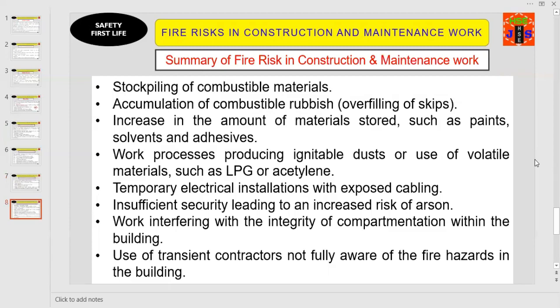To summarize, the key factors that may lead to fire or explosion in construction and maintenance work are: (1) stockpiling of combustible materials; (2) accumulation of combustible rubbish and overfilling of skips; (3) increase in the amount of materials stored such as paints, solvents and adhesives; (4) work processes producing ignitable dust or use of volatile materials such as LPG or acetylene; (5) temporary electrical installations with exposed cabling; (6) insufficient security leading to increased risk of arson; (7) work interfering with the integrity of compartmentation within the building.